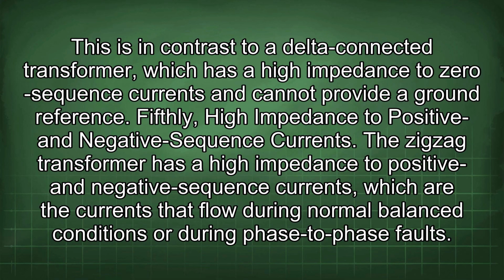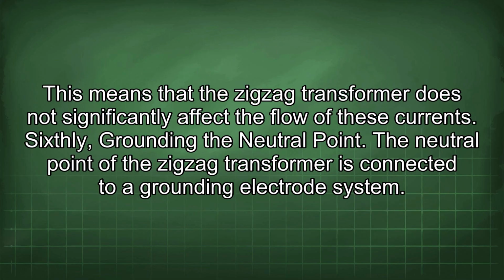The zigzag transformer has a high impedance to positive and negative sequence currents, which are the currents that flow during normal balanced conditions or during phase-to-phase faults. This means that the zigzag transformer does not significantly affect the flow of these currents.